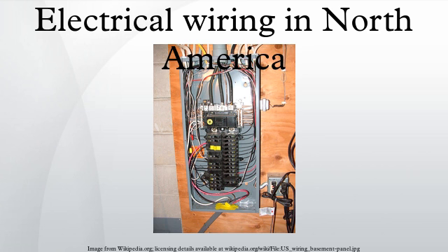Lighting and general-purpose receptacles are at 120 volts AC, with larger devices fed by 3-wire single-phase circuits at 240 volts. In commercial construction, 3-phase circuits are used. Generally, receptacles are fed by 120V or 208V, and can include special current-rated outlets for industrial equipment. Lighting is usually fed by 277V. Equipment can be hardwired into the building using either 120/208V or 277/480V.